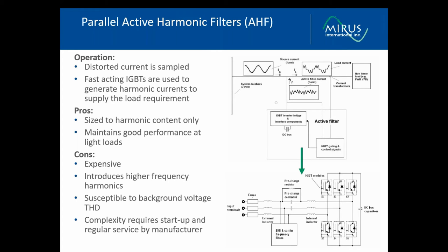We are starting to see more commonly the use of parallel active filters. These measure the current being drawn by the nonlinear load and supply the harmonic currents that are required by the load. So they will inject harmonic currents into the system that the load can draw so that the upstream current that the power system sees becomes much more sinusoidal.